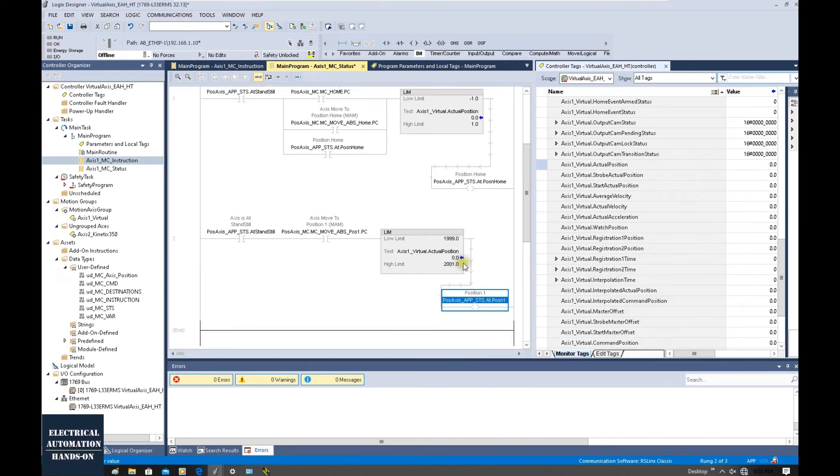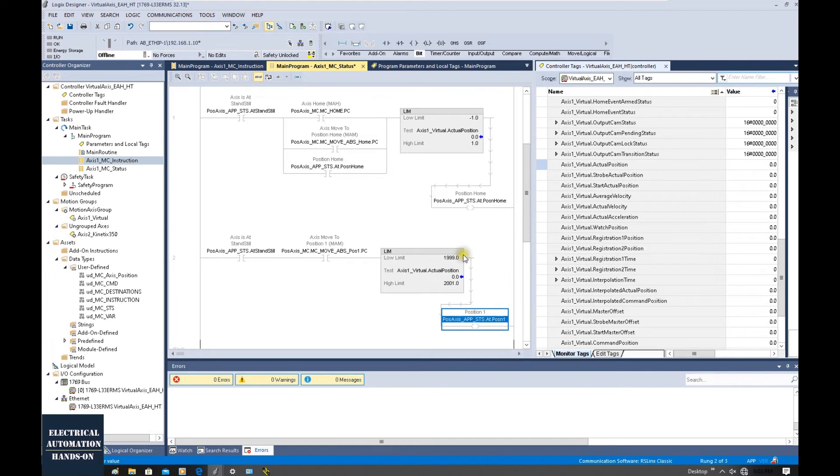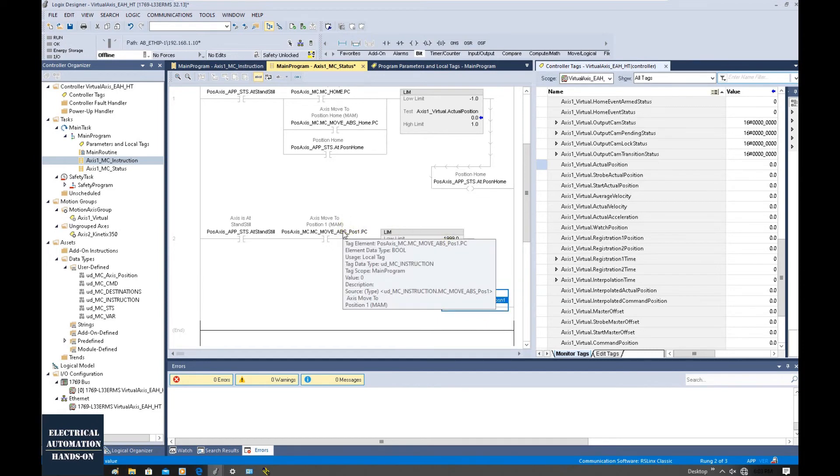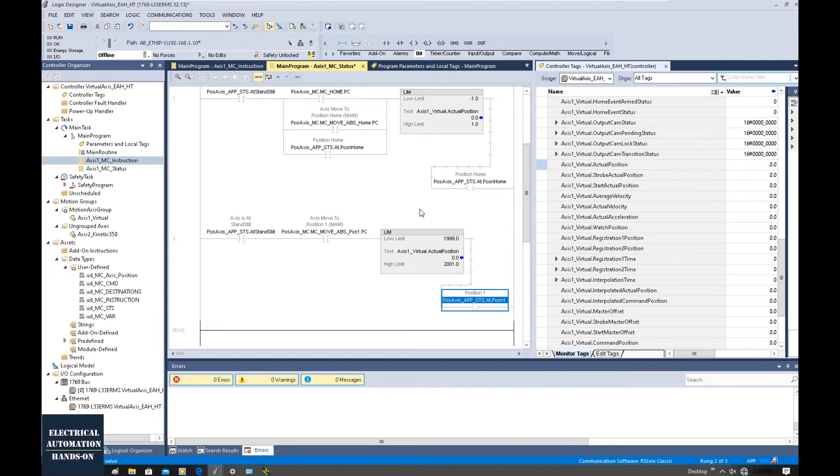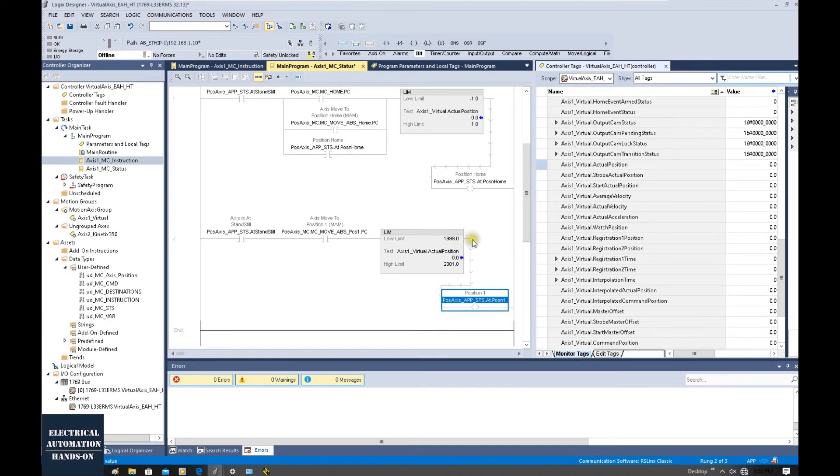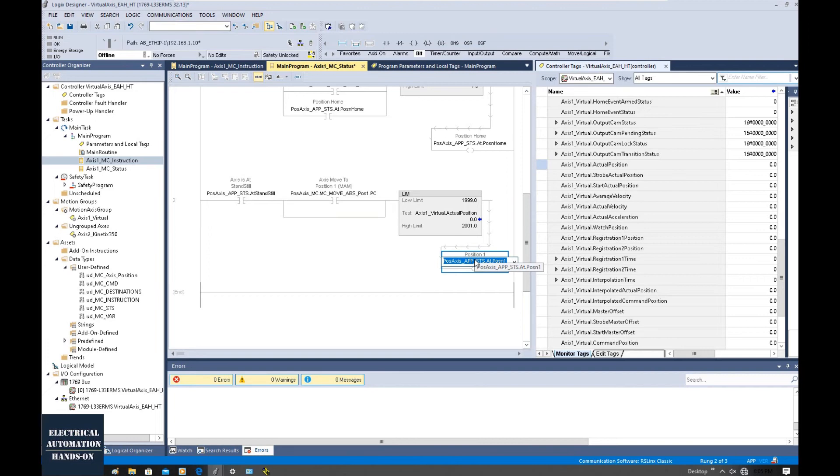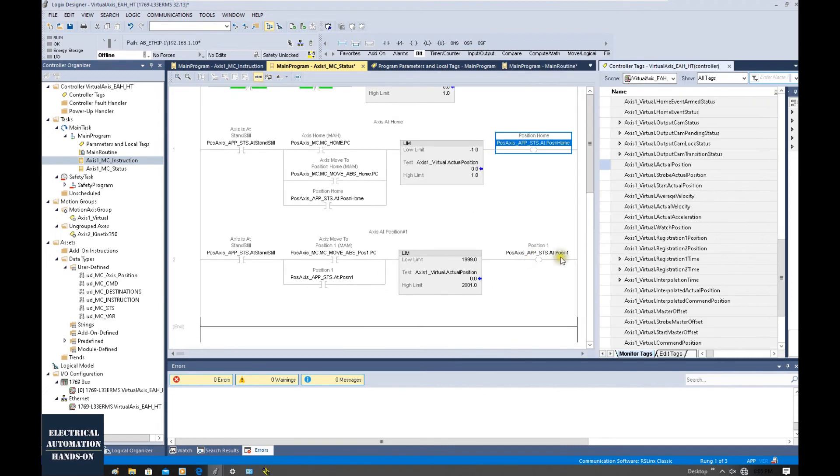Here I would like to mention one thing. Currently we're using fixed numbers running as a threshold. Ideally, we can use the variable. The variable can be based on our target position minus and plus a little bit of window. So if we change that target, this window also can be automatically changed to follow our target. That is easy for us to do the commissioning and the programming test. So using that variable will be very convenient. Don't forget here we can latch in this result. We will follow this style and program the position two and position three.